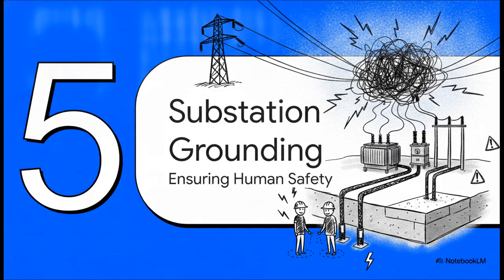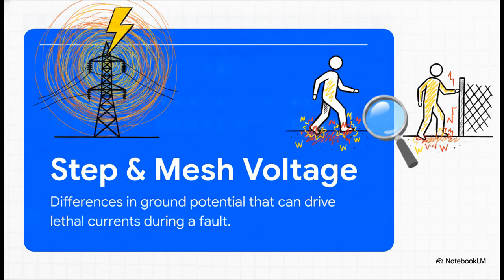Section 5. Substation grounding and safety. Finally, let's zoom all the way down from these huge macro-level challenges to just a single node, the substation. Because when grid instability leads to a fault, managing that massive surge of rogue electricity is literally a matter of life and death for the people standing on the ground. When a short circuit or a lightning strike hits a substation, the fault current dumps directly into the earth, and this creates something called ground potential rise, meaning the actual dirt you are standing on can carry vastly different voltage levels from one spot to another.